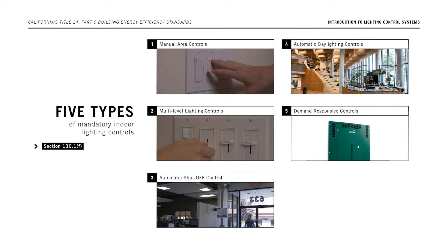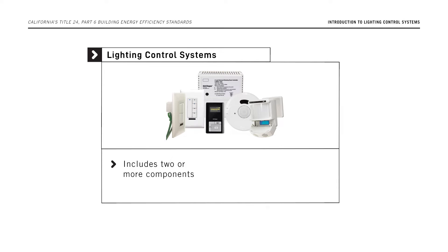The Energy Code outlines how each control system should operate to make sure that all functions of the mandatory lighting controls are permitted by the system when working together. Lighting control systems include two or more components. A Certificate of Installation, NRCI-LTI-E, must be submitted for projects where energy management control systems or lighting control systems are installed to certify compliance with the energy code.